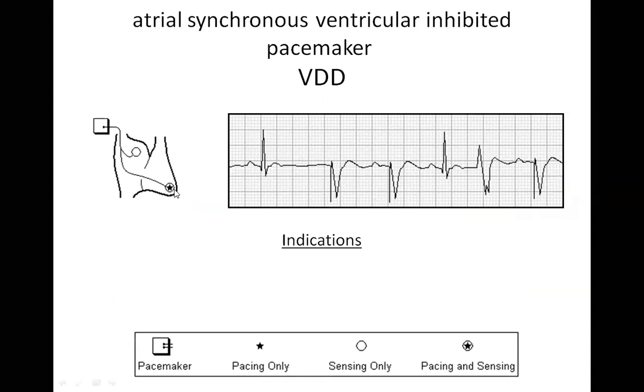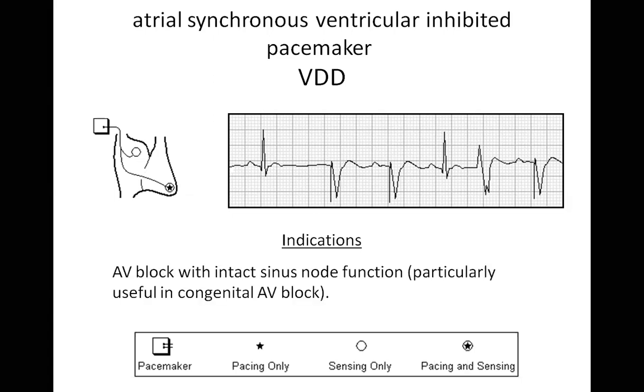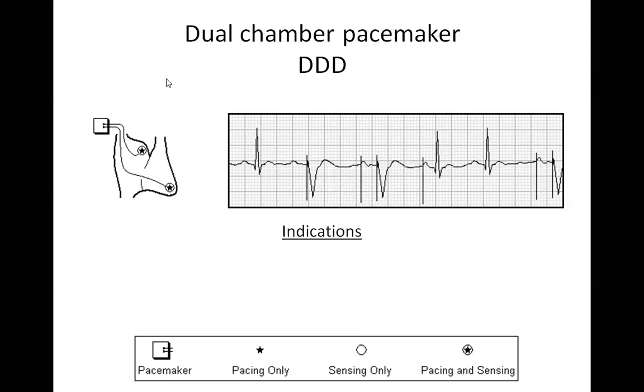Yes, sir. So you can see on this slide that there is a single pacing lead, which is in the ventricle, but the one in the atrium is not pacing but sensing. So it's still a single lead, but the ventricular lead is the only one pacing, and the atrial lead is sensing. So you're using the ventricular lead to track the atrium. It can be functioning, and you'll be thinking it's a double chamber pacemaker like this. Unlike this double chamber pacemaker, there's a pacing lead in both atrium and ventricle, so they can still communicate.